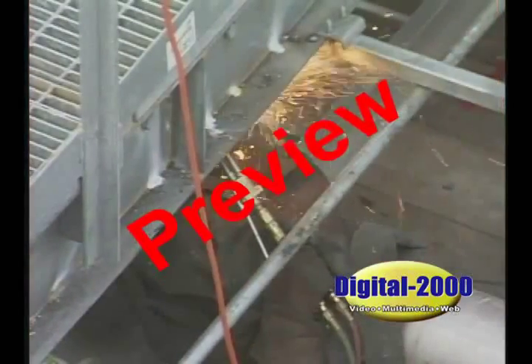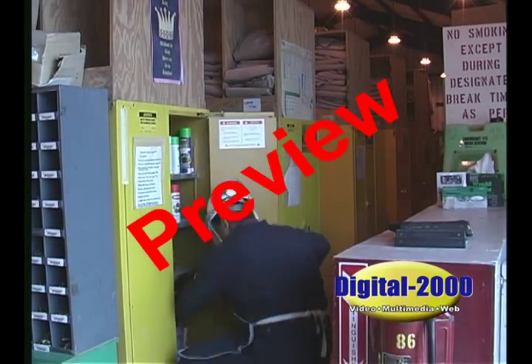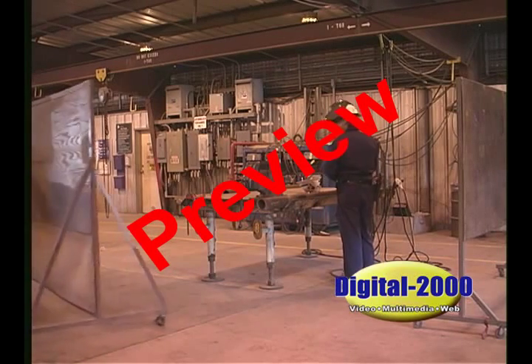Naturally, the floors must be swept clean of combustibles. Combustible floors should be wetted down and covered with damp sand or fire-resistive sheets. Flammable liquids removed. Other combustibles, if not removed, must be protected with fire-resistive tarpaulins or metal shields. Explosive atmosphere in the work area must be eliminated. All wall and floor openings covered. Fire-resistive tarpaulins suspended beneath work.